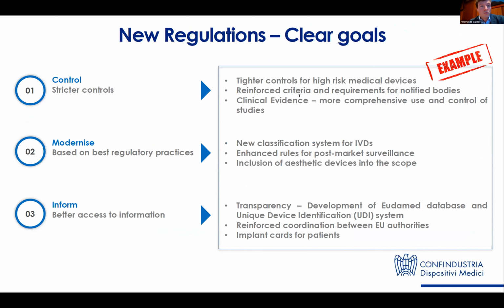What's the goal of these two new regulations? Basically, the aim was to implement stricter controls, especially for higher-risk medical devices. This will be done through a reinforced role of the notified bodies, which are independent bodies designated by competent authorities to release certificates to put a device on the market, and more controls, thanks to more clinical evidence required from manufacturers to support the mechanism and mode of action of the device they want to put on the market.